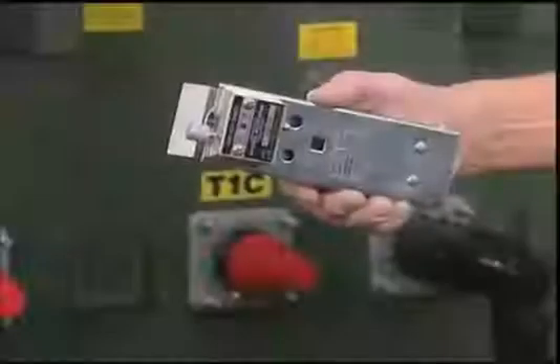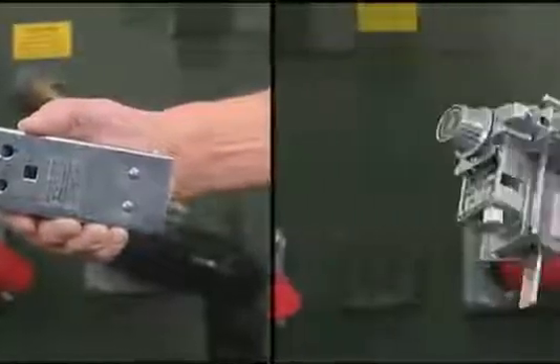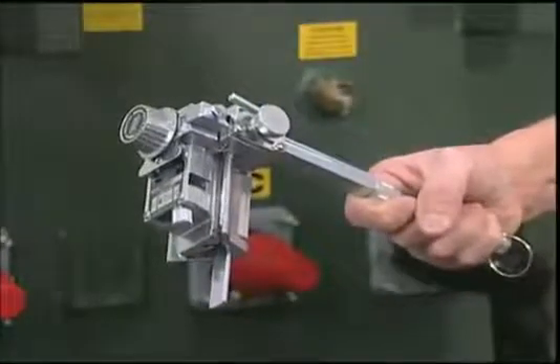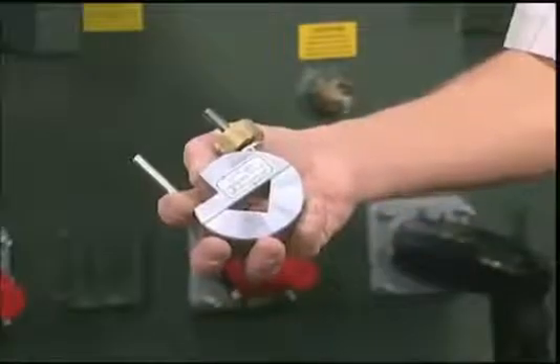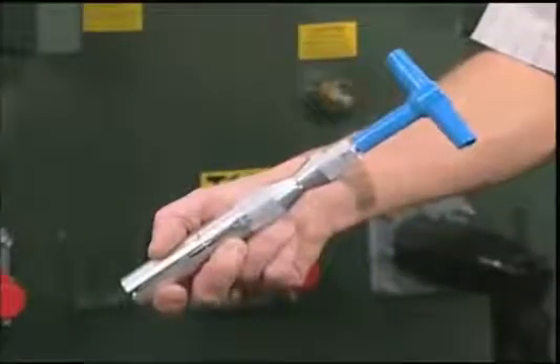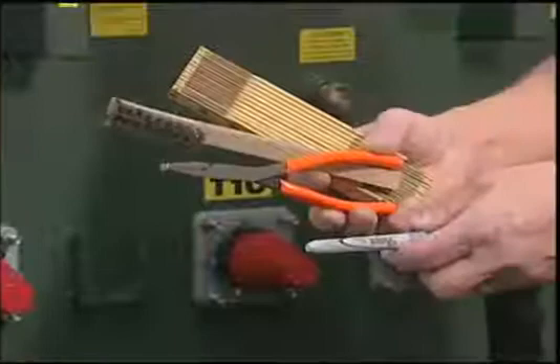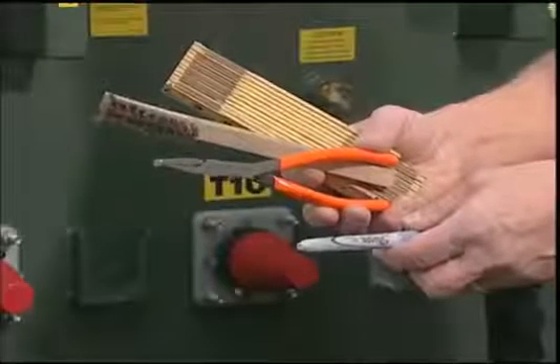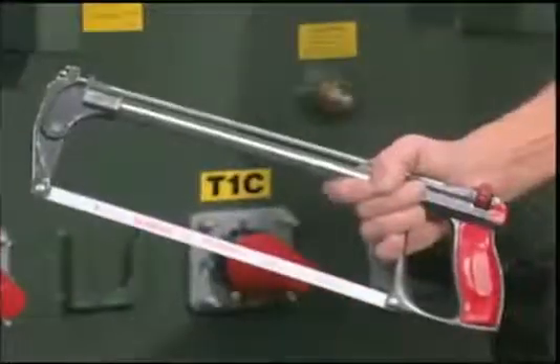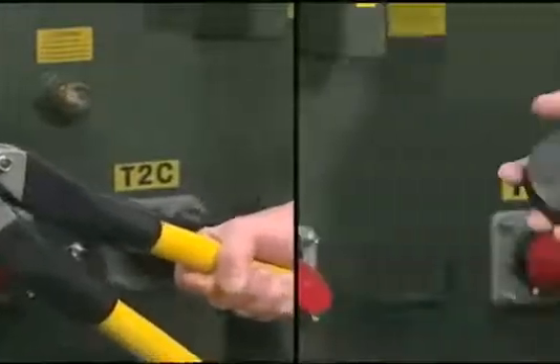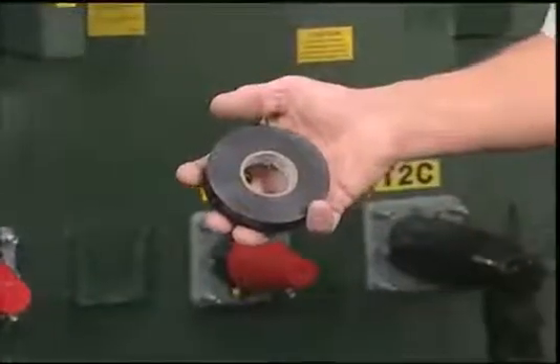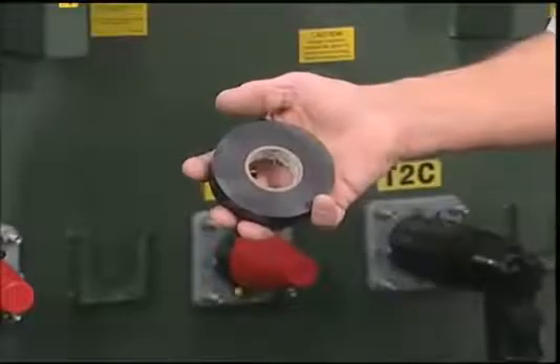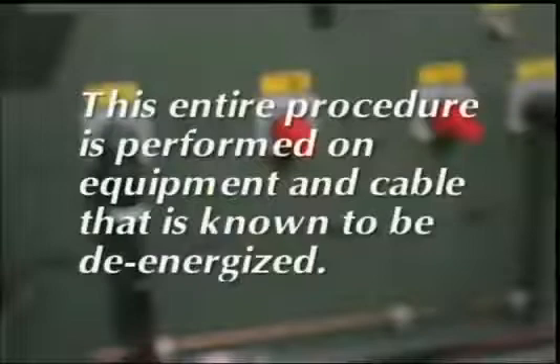Specialized cable preparation tools are used. These include a tool for removing the cable jacket and insulation shield, the cable insulation removal tool, the insulation chamfering tool, and the probe installation torque tool. Also needed are a ruler, wire brush, pliers, marking pen, hacksaw, and crimp tool. On elbows with the integral jacket seal, PVC tape is also required. And of course, the entire procedure is performed on equipment and cable that you know to be de-energized.